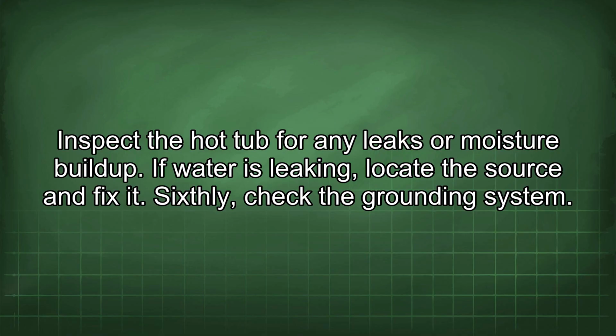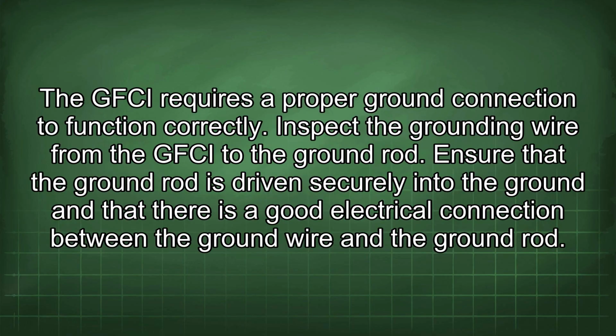Sixthly, check the grounding system. The GFCI requires a proper ground connection to function correctly. Inspect the grounding wire from the GFCI to the ground rod. Ensure that the ground rod is driven securely into the ground and that there is a good electrical connection between the ground wire and the ground rod.